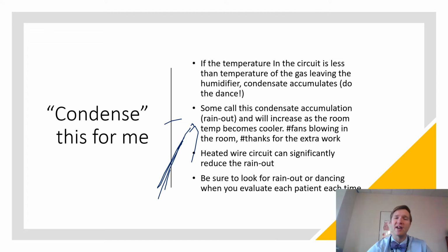To help avoid that condensate, so that way they can have their heater on at night with their CPAP or nocturnal BiPAP, and not have a bunch of water that forms and just gushes and gives them a little bolus of fluid every couple of hours. So we need to be creative in making sure that's appropriate. The other thing too is there are circuits that have water traps in them, and that might be appropriate if we have this issue, especially if it's a room that's really drafty or a patient that we're having to blow fans on, right? We need to look at what we're having to do to help this overall situation.